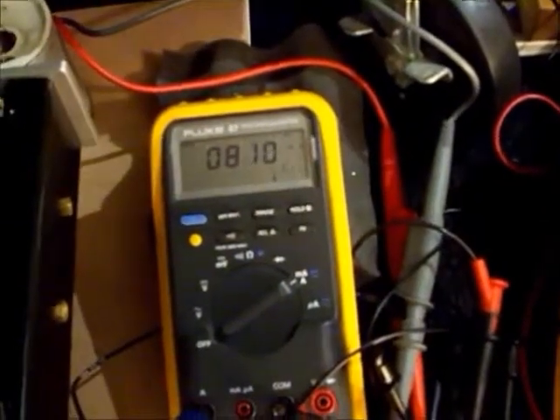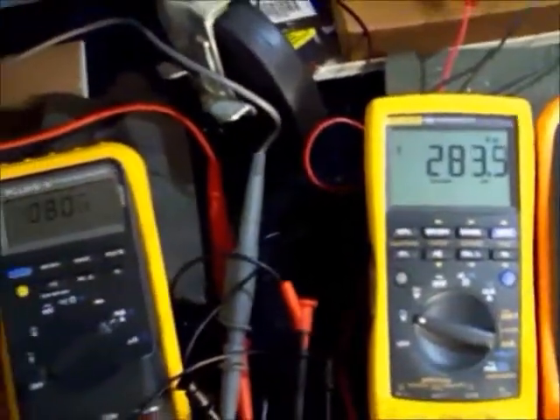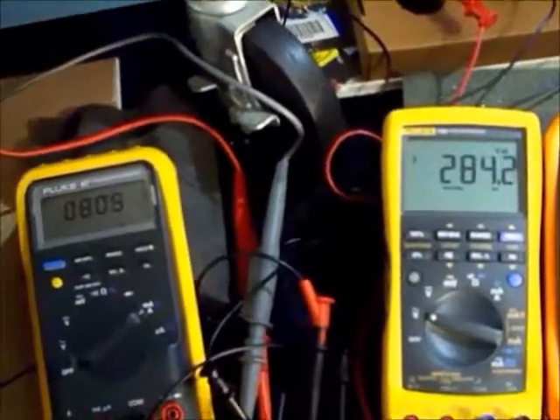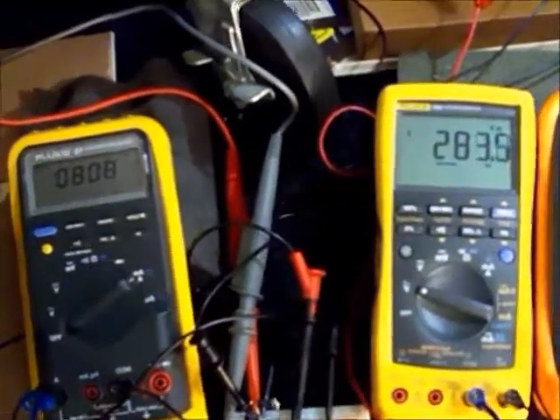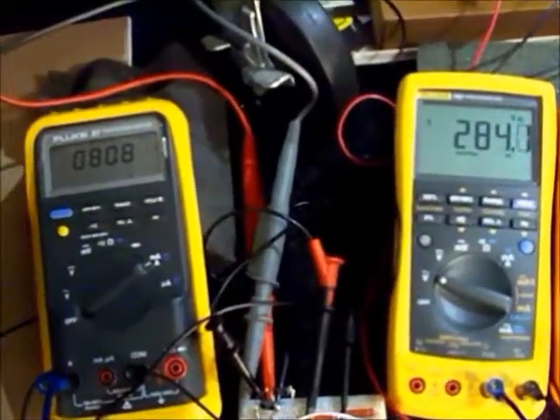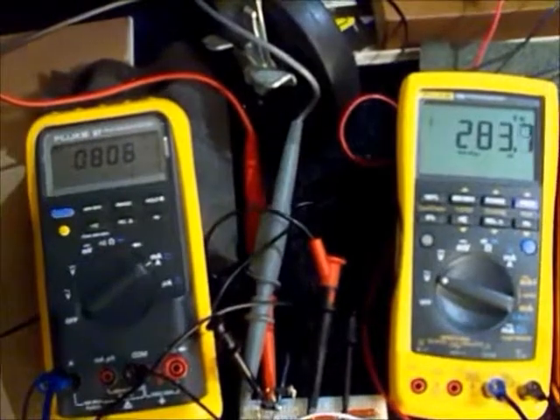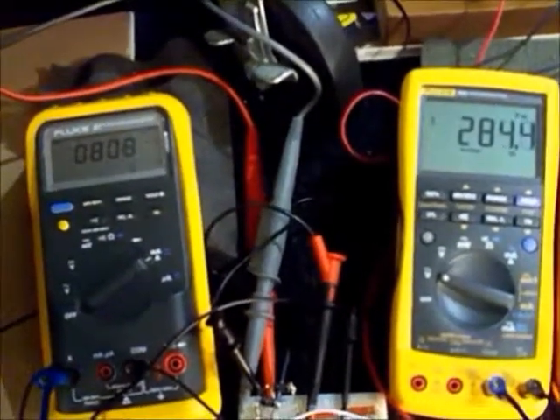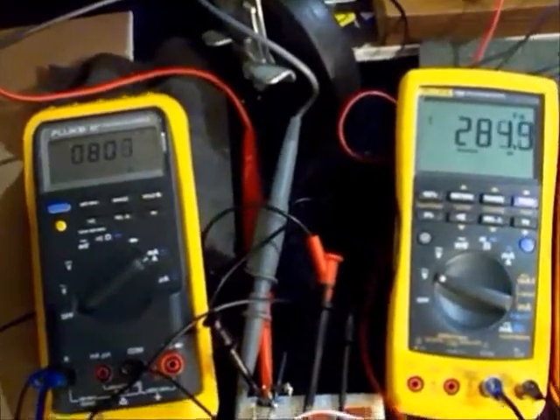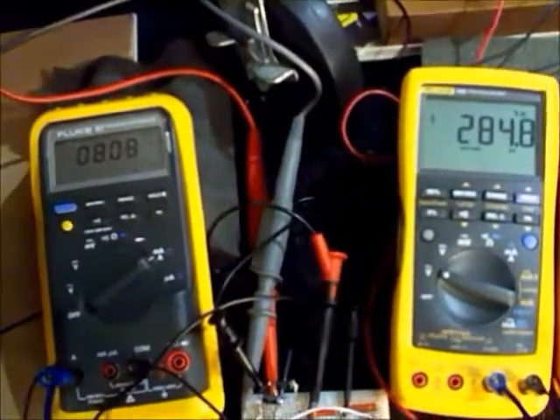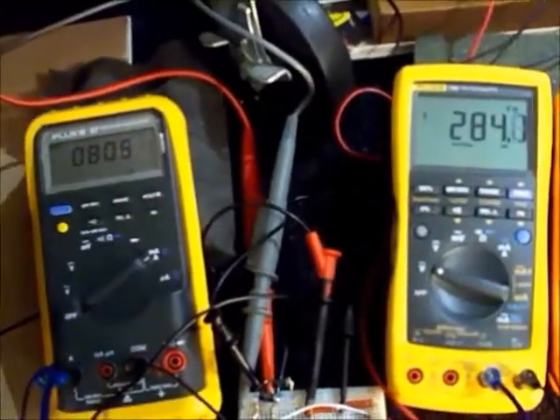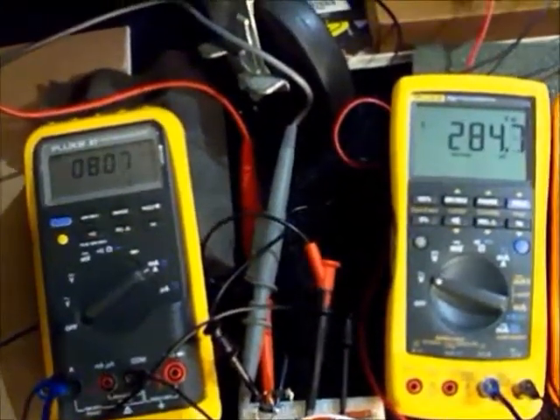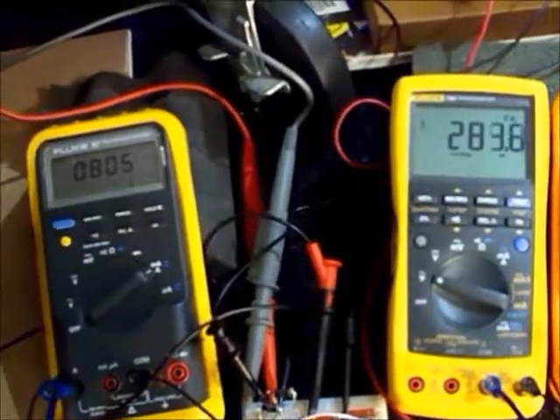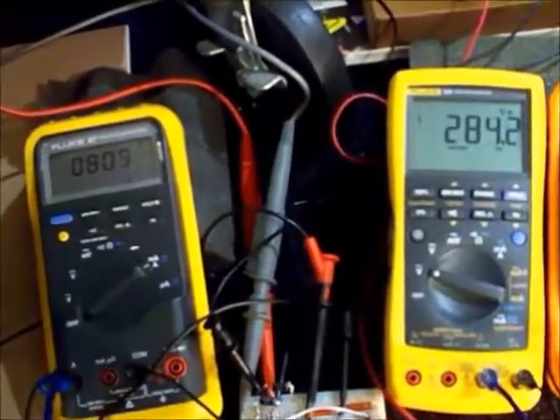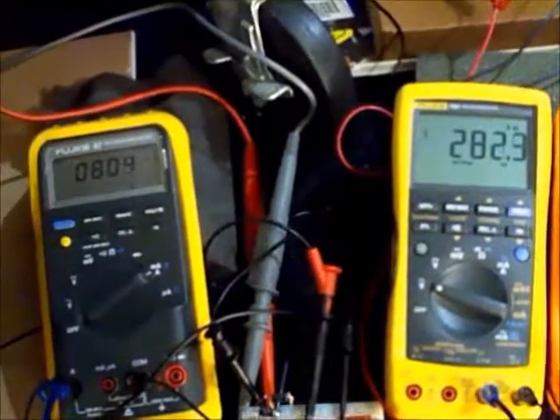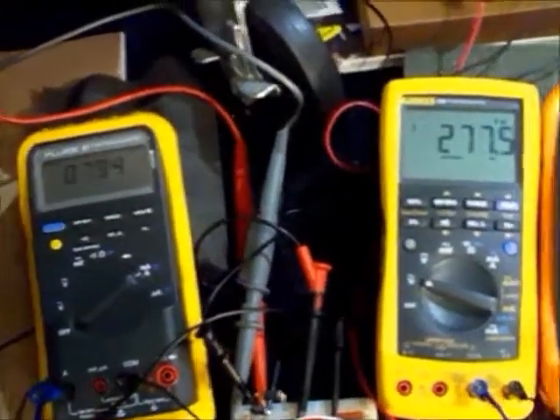808.9 milliamps at 284 volts. There's a data plate on the transformer, and it says it's good for 300 milliamps, 300 volts. So obviously at 800 we're drawing a little bit more than 300, and our voltage has dipped to 284. Now that's AC volts, and that's AC milliamps.